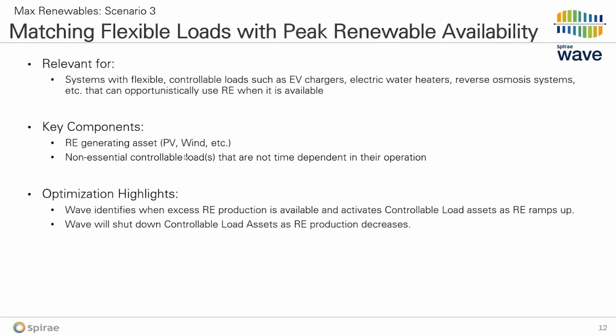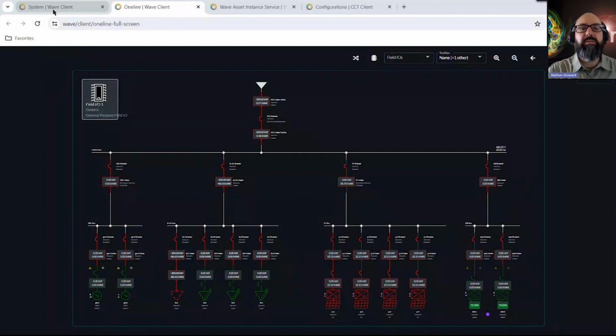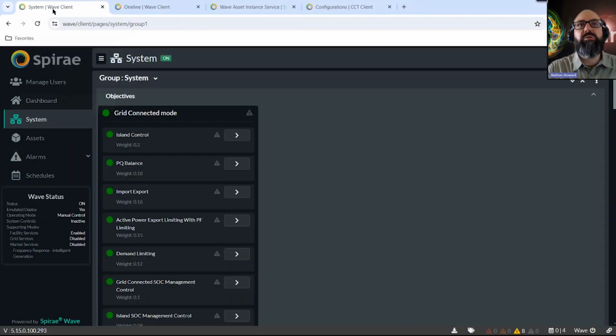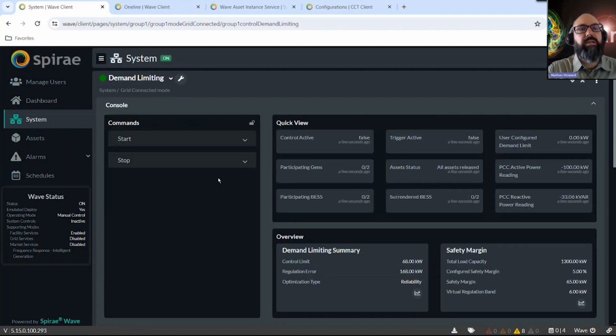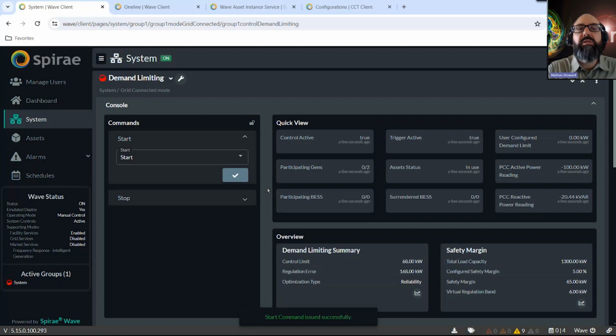So in this scenario, we'll switch back to our demonstration. And we're going to look at a little bit of a different control here. In the previous example, we were looking at that net zero limit, but if you maybe don't have that constraint or there are other things you're looking at, you might want to use demand limit. So this is kind of the 180 flip of that, where as a facility operator, you might want to be using as little power as possible from the utility. You want to reduce your energy costs, your energy bill, and so we're going to take advantage of the demand limiting control. So we'll go ahead and get that started.